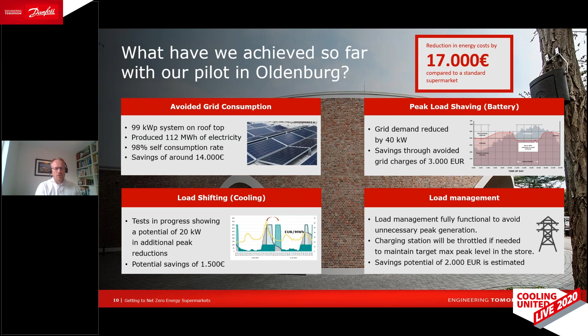Finally, we can transform the store into a power station. The last bit to get down to zero net uses the refrigeration system to its full potential. In areas with district heating, or where the store is in an apartment building, offices, or shopping centers, you can actually use the heat from the refrigeration system. In fact, the refrigeration system is a 60 kilowatt system, and on average it's only using maybe 20 or 30% of that capacity, because it's dimensioned for the warmest day of the year.